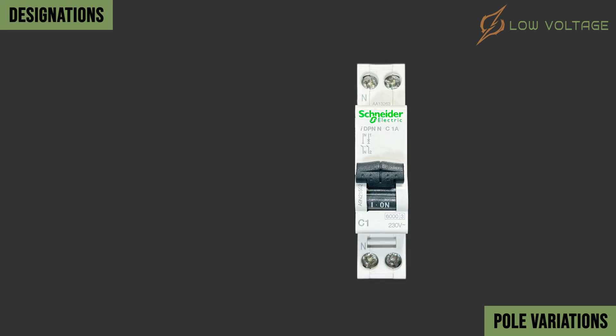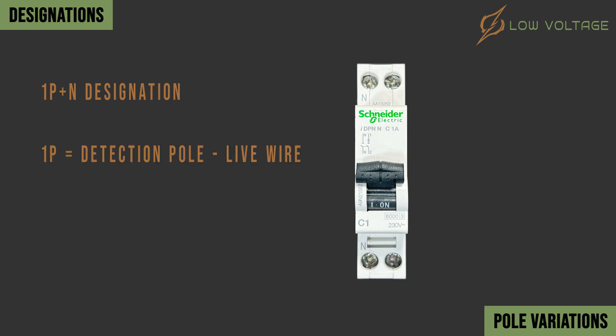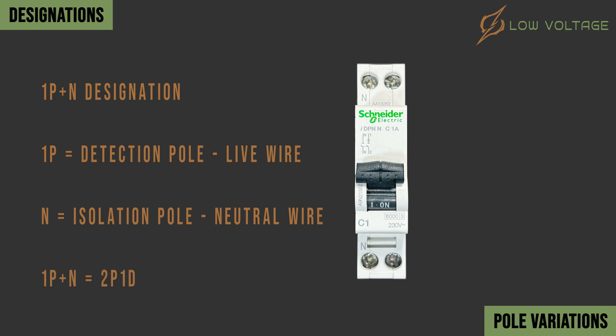This is a one pole plus neutral MCB, having a 1P+N designation, so it can be considered as a two poles MCB. One is for detection used for the live wire, and the other is for isolation used for the neutral wire. So it can also be defined as two poles, one detection, or 2P1D, having one detection symbol and one isolation symbol.